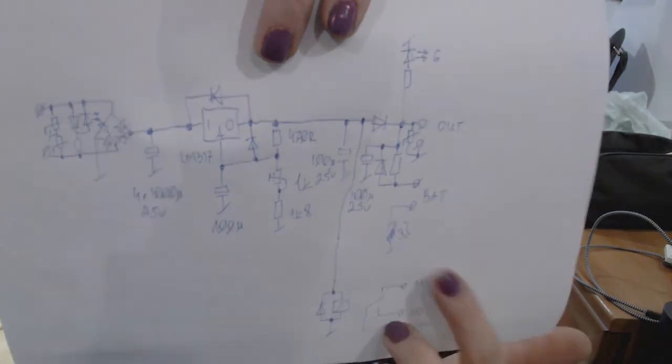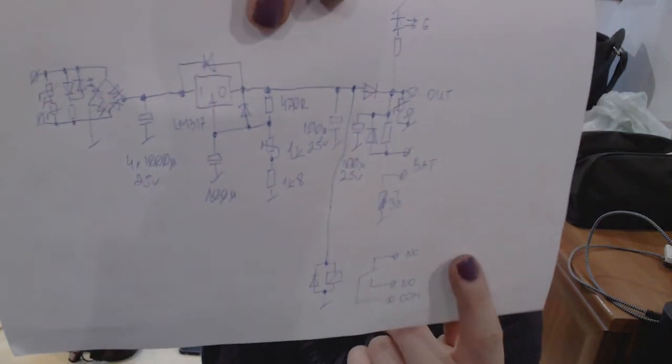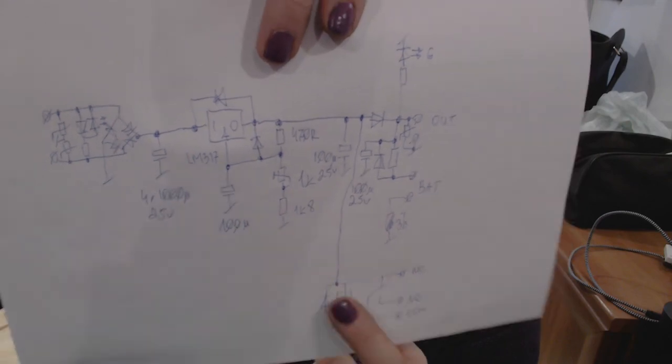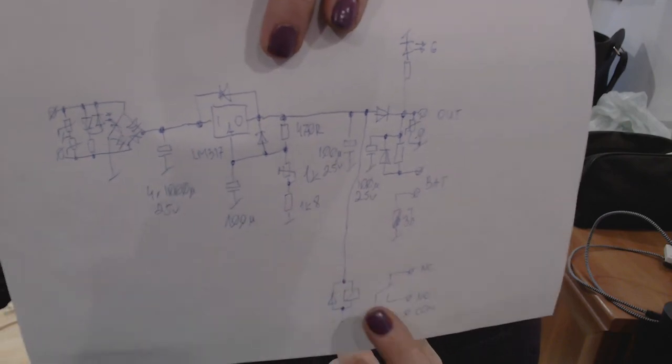It's the current limiting circuit for charging the battery, and there's an additional relay for indicating the mains power presence for the alarm circuits, because this module was made by Pulsar. It's a Polish company that specializes in video monitoring and alarm electronic solutions. So having information from the power supply that it's on AC or battery power is pretty important in an alarm system.